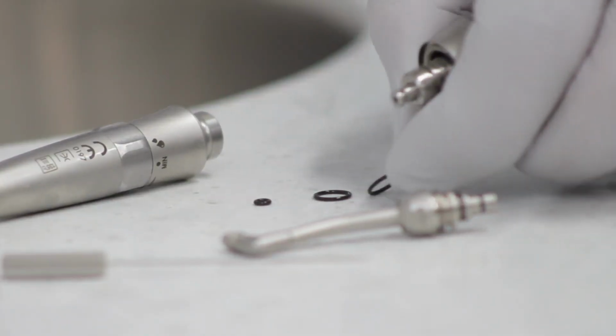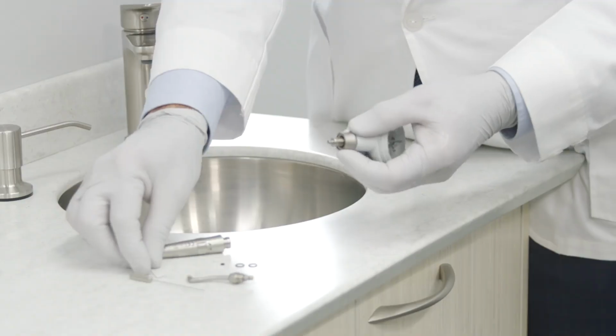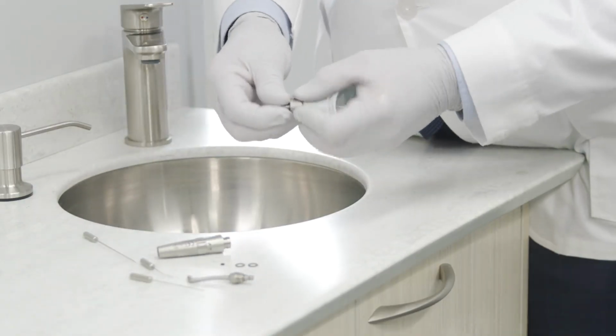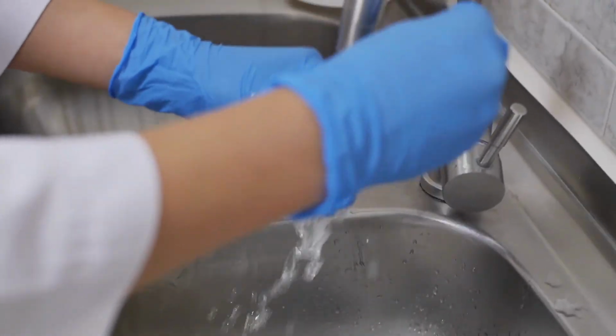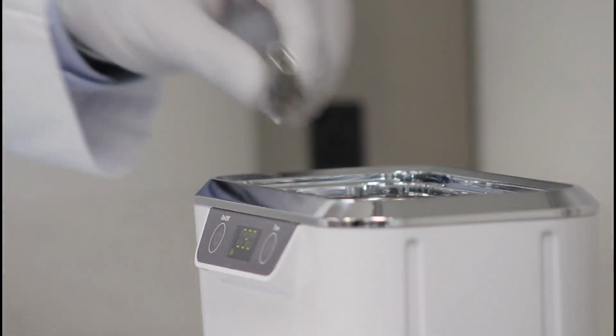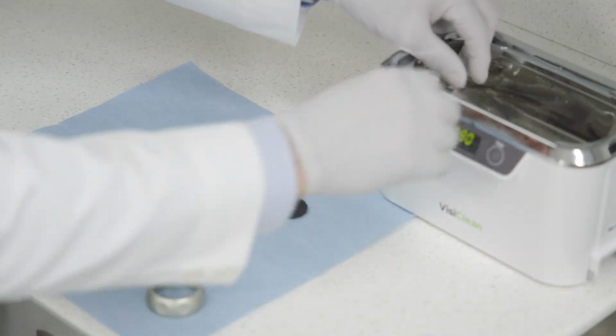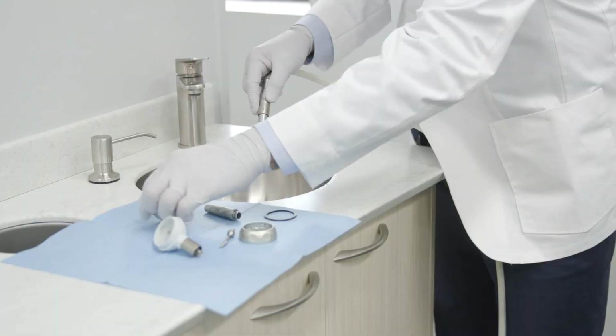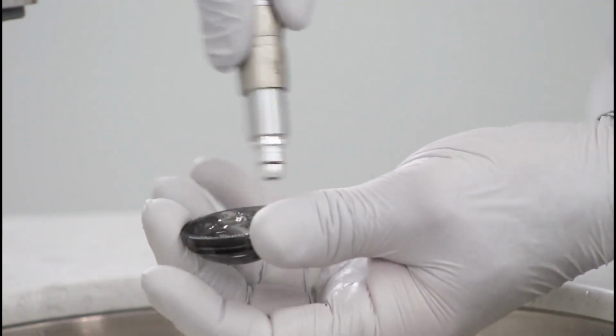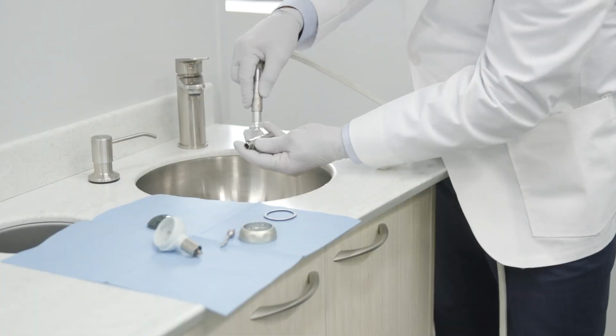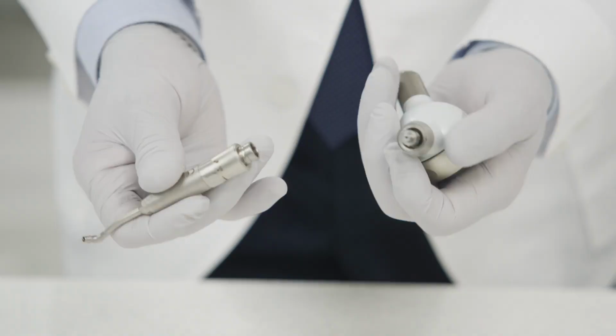If powder is stuck to the O-ring section, remove them and clean the O-rings and grooves carefully. Rinse all the parts under running water. You can also perform ultrasonic bath cleaning with hot water. Blow water off all the parts and pieces such as case cover, handpiece and nozzle, and let air dry. Reassemble.